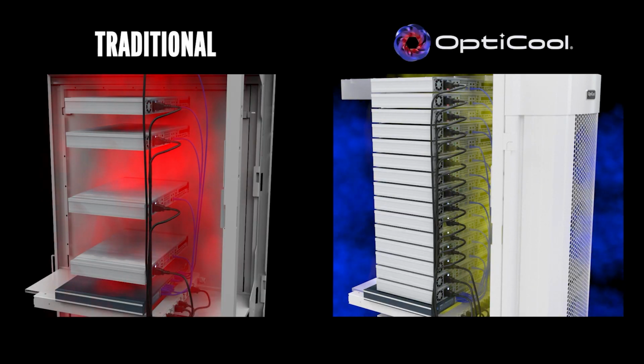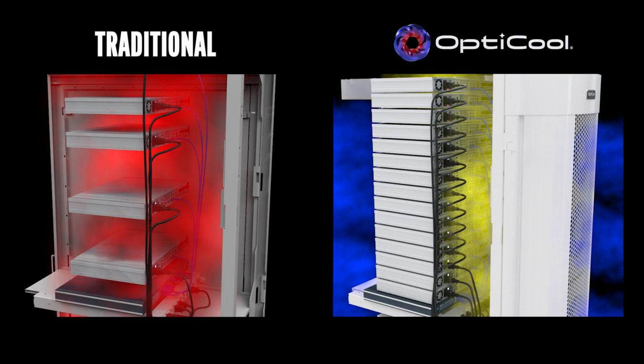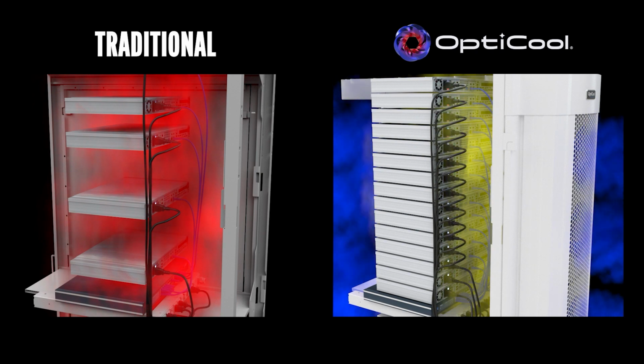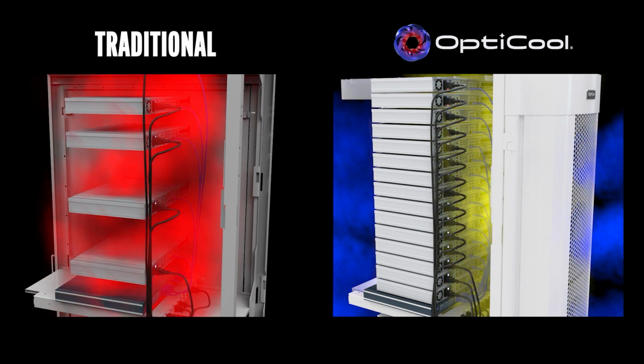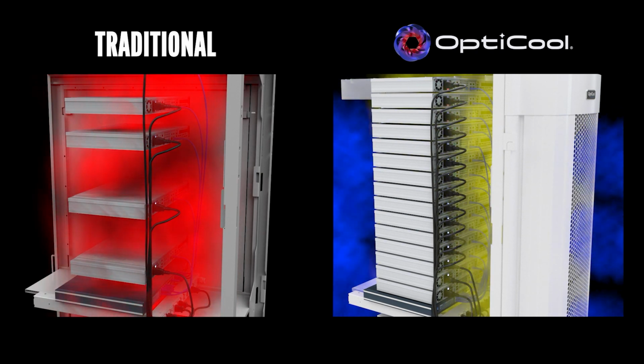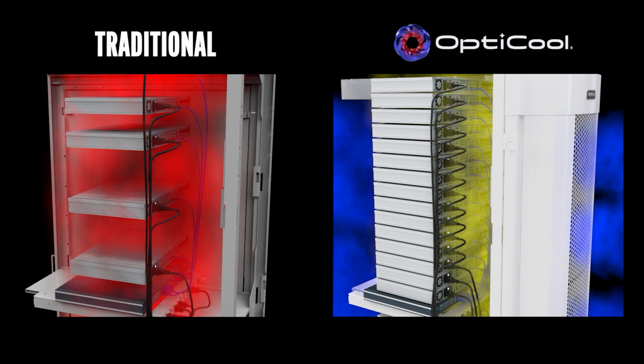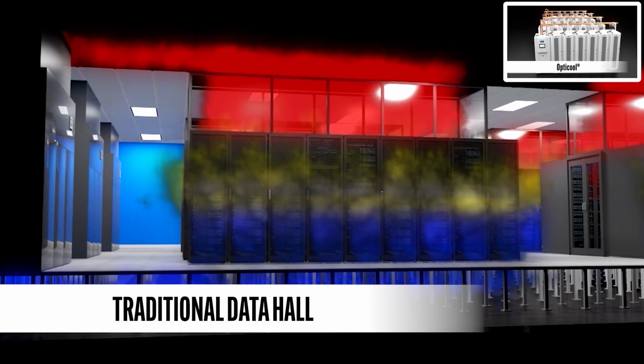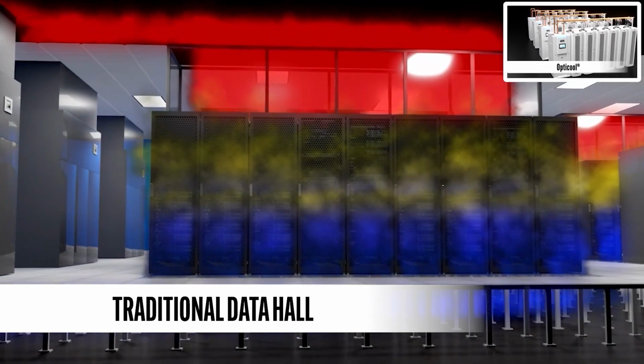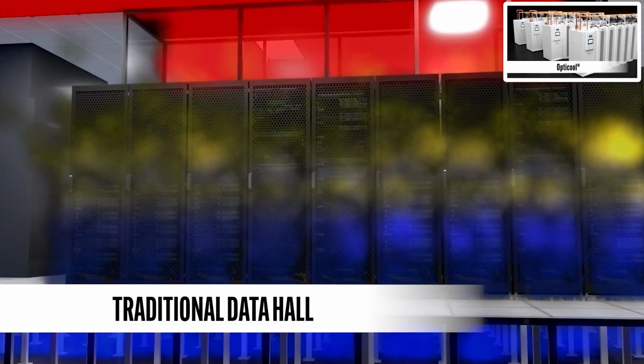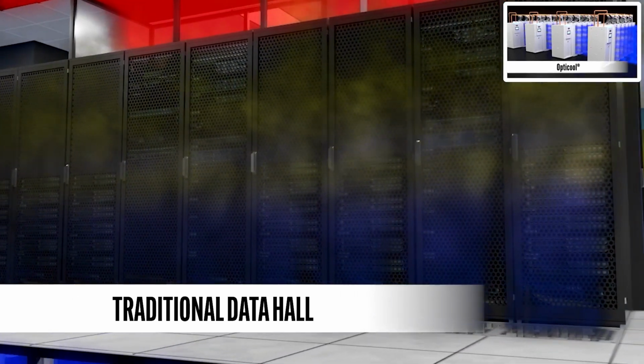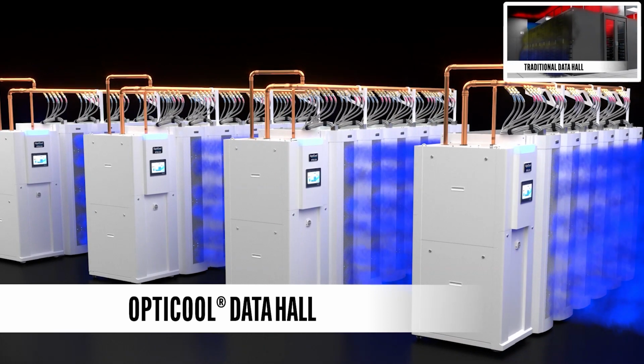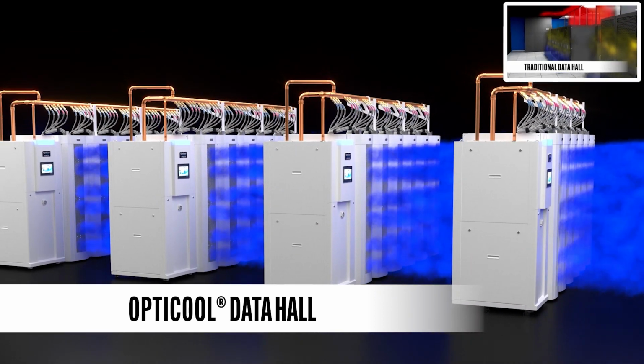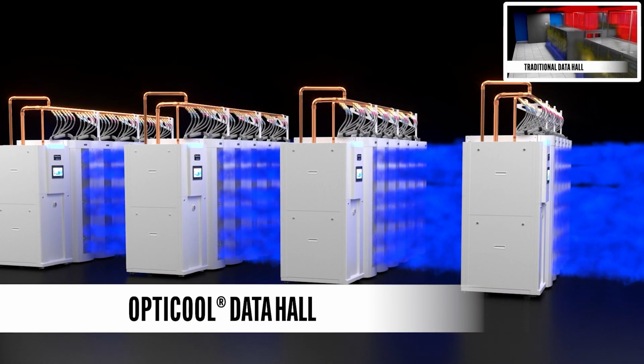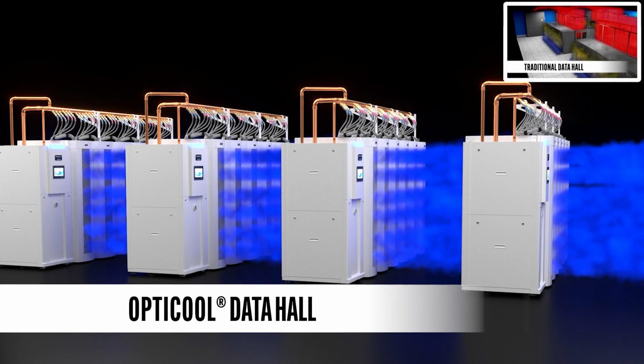So in a traditional data center with traditional CRAC units, you cannot direct the cooling where it needs to go. Because you have to increase that space, you lose real estate. Where in the traditional, I'm just trying and hopefully pressurizing it enough to get it where it needs to go. In the OptiCool design, I'm pushing it into the front and pulling it out the back. So I'm directing it exactly where it needs to go.